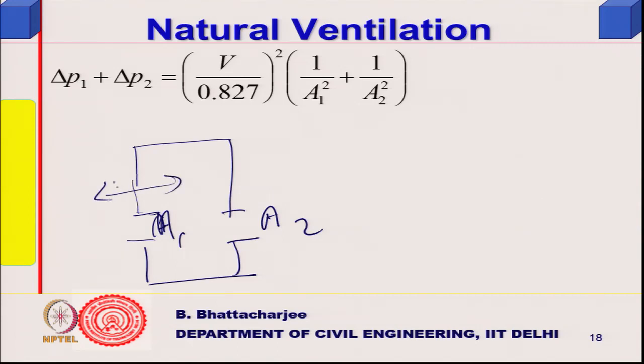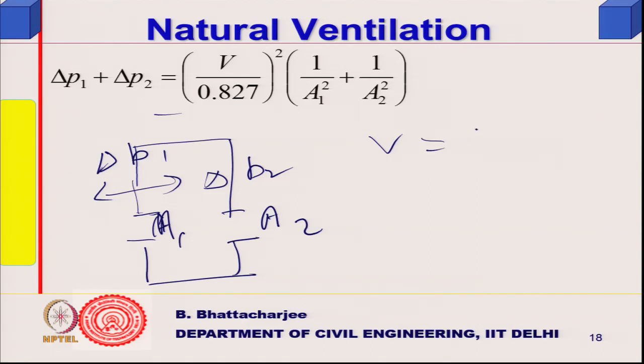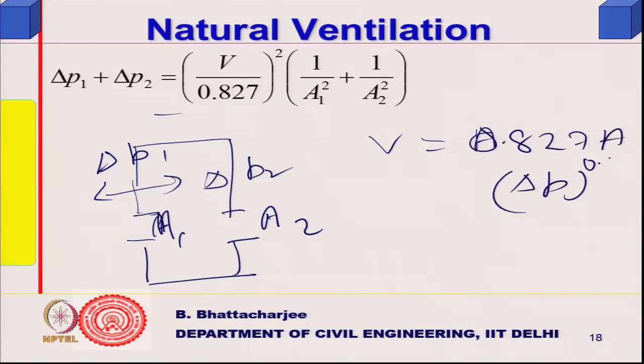Delta P1 is the pressure difference at the first opening, delta P2 at the second. The total flow uses the formula: flow equals A times 0.827 times delta P to the power 0.5.